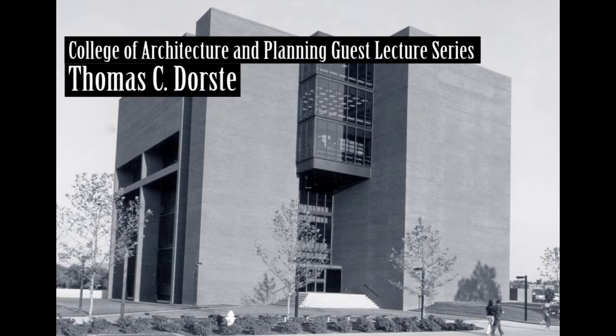And we'll do the same thing on the perimeter with units, here again, still using the variable volume, but adding to the variable volume system a fan box which would work independently of the variable volume and recirculate the air from the plenum space back to the occupied space and shut off all outside air and shut off the entire variable volume system. This took the next step, and we got the total energy in that building down to 54,000 BTU per square foot per year, which is about 1,000 BTU less than the current government standards for targets.